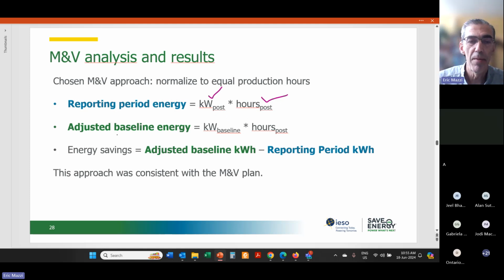And then what we did for the baseline is we took our baseline kilowatt, our average powers, and we multiplied by the same hours as the post. And that came up with our annual energy savings. Kilowatt times hours is kilowatt hours. We get two numbers, we subtract them. This was consistent with what was in the M&V plan.